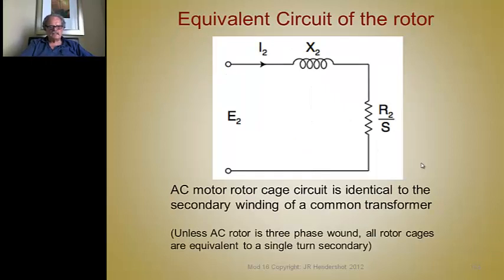And the rotor cage has the same circuit as the secondary of a common transformer, and the rotor cage is treated as one circuit for the rotor because it's equivalent to a single turn secondary. It doesn't have 3 phases, it's only got 1 phase, even though the 3 phases of the stator field will induce the right number of poles in the windings of the rotor.